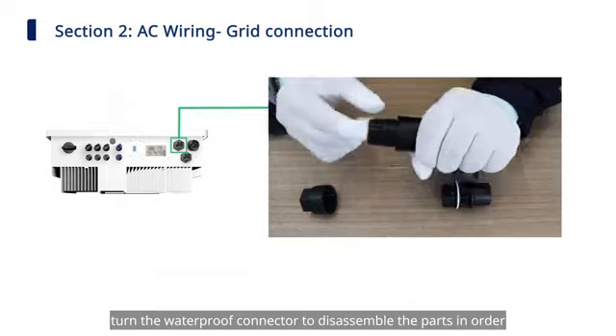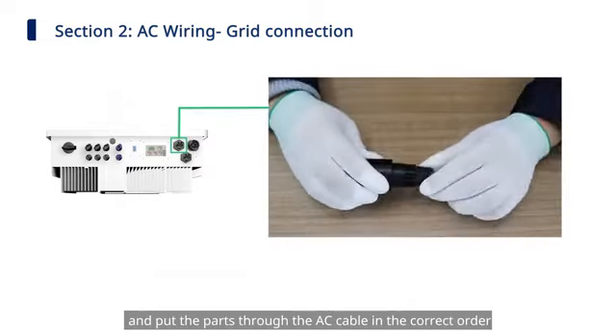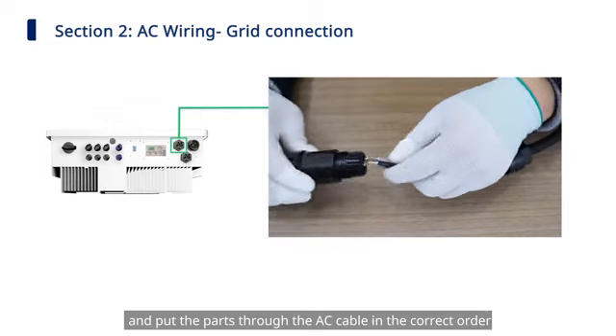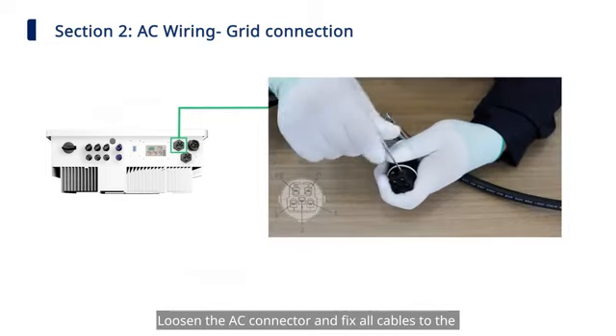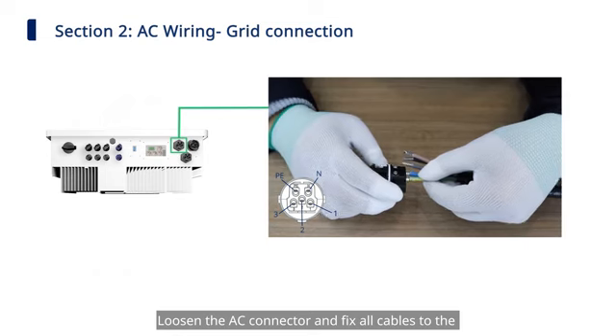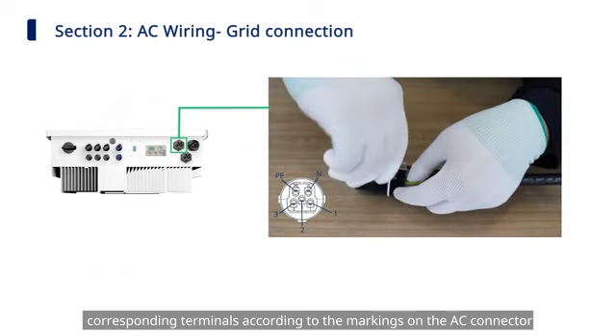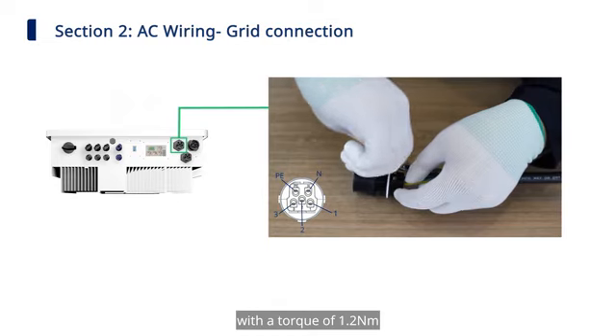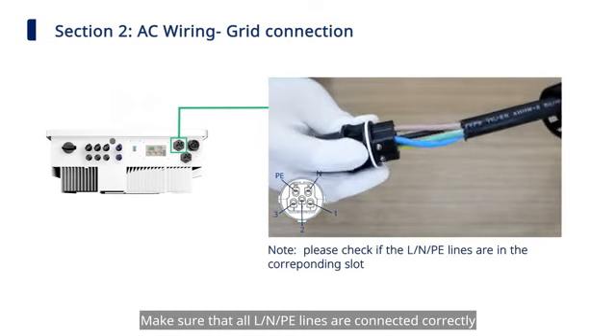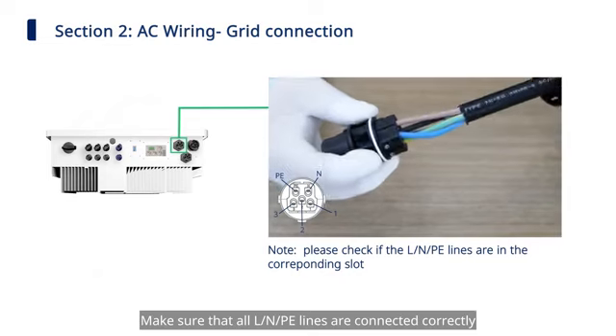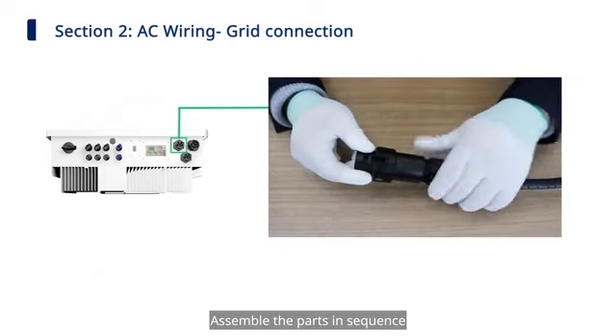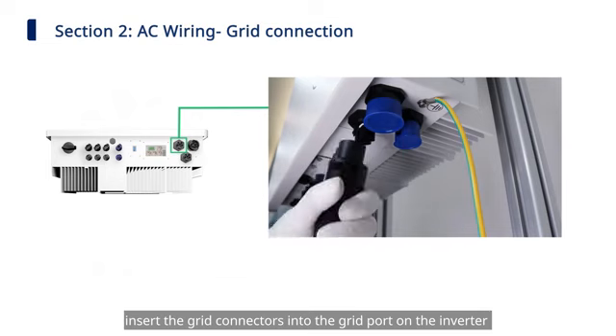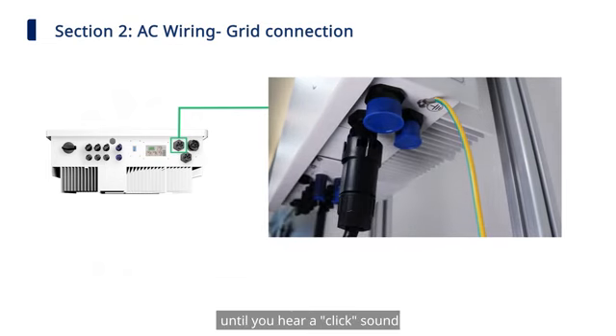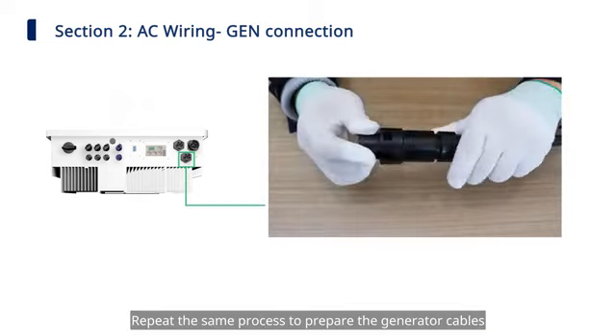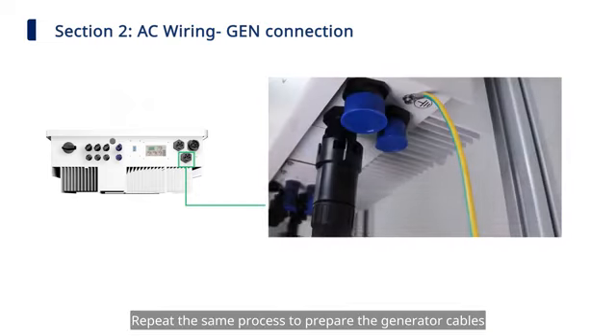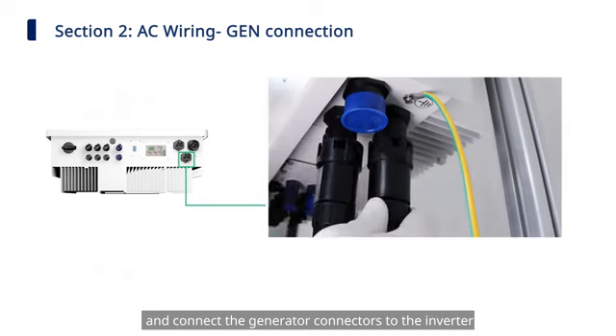Next, turn the waterproof connector to disassemble the parts in order and put the parts through the AC cable in correct order. Loosen the AC connector and fix all cables to the corresponding terminals according to the markings on the AC connector, with a torque of 1.2 Newton meters. Make sure that all L, N and PE lines are connected correctly. Assemble the parts in sequence. Finally, insert the grid connectors into the grid port on the inverter until you hear a click sound. Repeat the same process to prepare the generator cables and connect the generator connectors to the inverter.